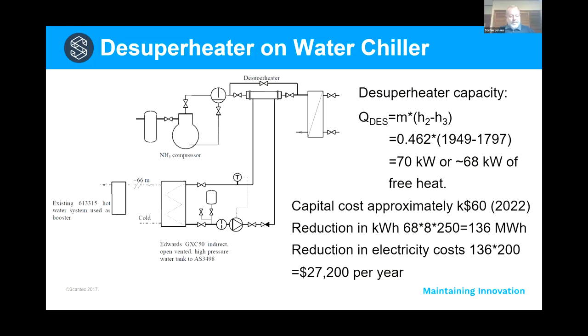And then you see down the bottom here, we have another heat exchanger. That heat exchanger sits between the water we actually consume, the water that comes out of the taps, and the closed water circuit that we circulate between that heat exchanger and the desuperheater. We are required to have a double heat exchange for domestic hot water services. But we also need that water-to-water heat exchanger that you can see there. That's the one, if you can see my cursor, this rectangle here.